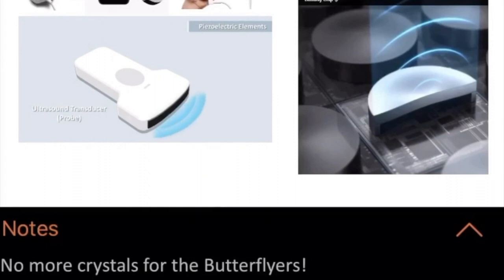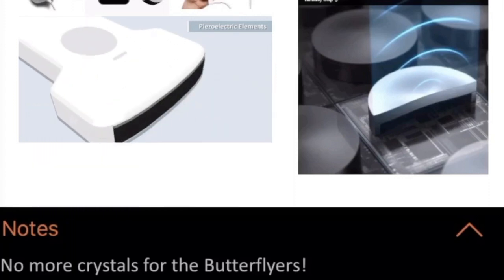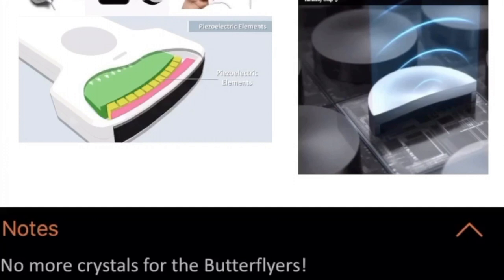This is how most of the ultrasound machines work. You have the ultrasound machine itself, you have the probe. The machine sends electricity to the probe, the probe converts it into ultrasound waves and sends it to the subject, and then part of these waves will go back to the probe, and then the probe will receive it and convert it back to electricity, and that will go to the machine, which will be displayed as a black and white picture.